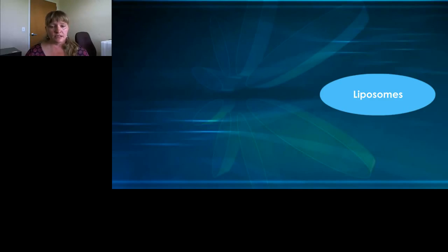The next calibration standard is the liposome. Liposomes can be purchased with different lipid configurations in different sizes. In the next video, the stained DiI liposomes are visible on the instrument touchscreen panel.